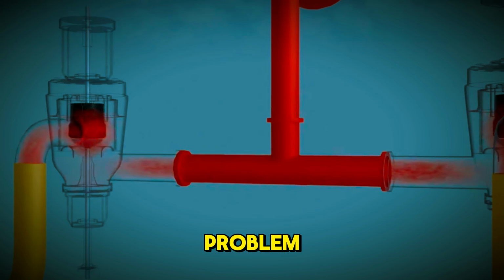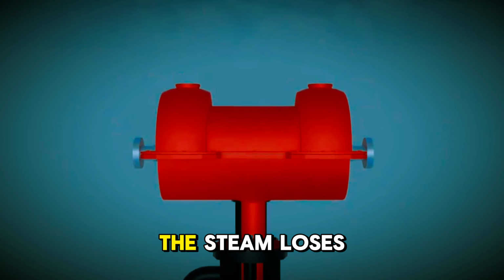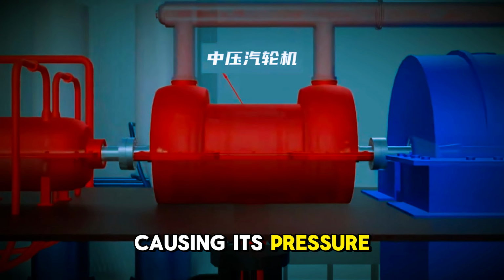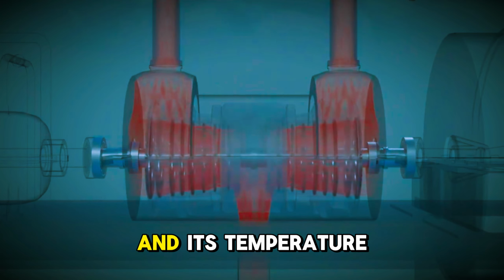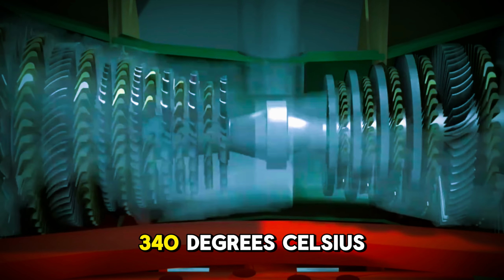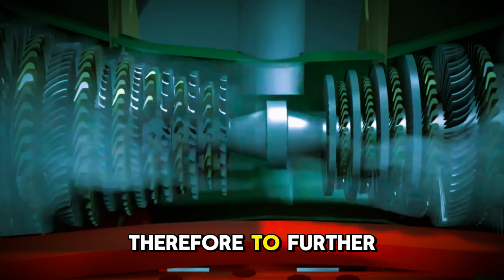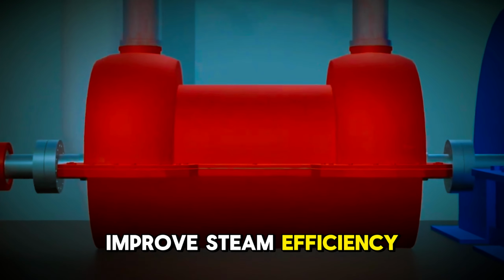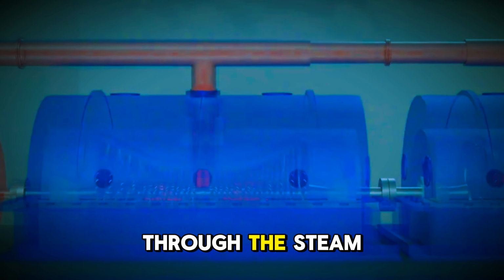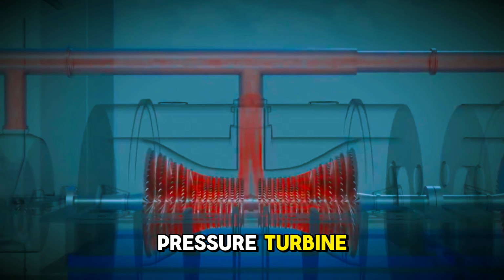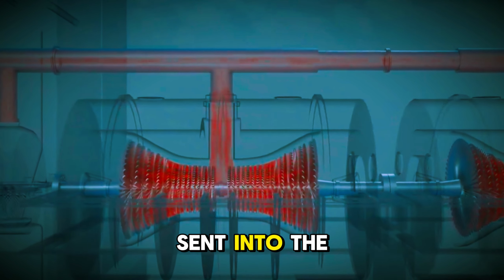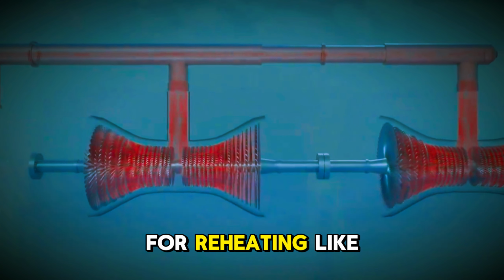However, there's a problem. After impacting the blades, the steam loses energy, causing its pressure to drop to just 85 bar and its temperature to fall to 340 degrees Celsius. Therefore, to further improve steam efficiency, the spent steam then flows out through the steam pipes at the bottom of the high-pressure turbine. This steam is sent into the reheater inside the boiler for reheating.